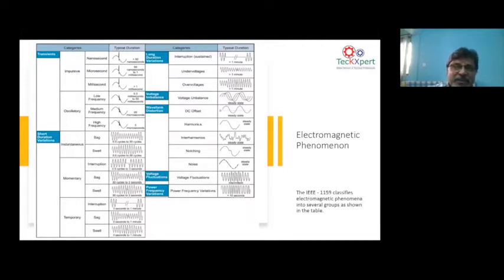So that sag will be for a very short period of time, because by the time your circuit breaker disconnects the fault and maybe the reclosure reconnects, you will see that in milliseconds the sag is gone. That means these sags need not last beyond one cycle. One cycle is 20 milliseconds, so it could be below 20 milliseconds. Sag, swells, short interruption, sudden interruption where power suddenly goes and comes back. These are all considered short duration variations of voltage.